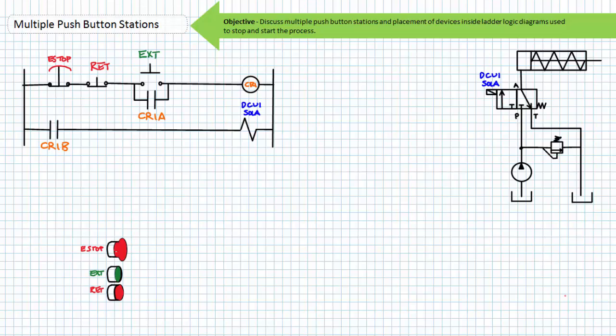That's the point of the holding circuit — it maintains the last asserted state. The cylinder would extend until the limits of travel and the pressure relief valve would open. To retract the cylinder, an operator must press the normally closed retract button. The now-open retract would de-energize the CR1 coil and the associated contacts would return to their de-energized state. The CR1A holding contact would open and remove the path in parallel to the extend push button. The CR1B contact would open, which would de-energize the A solenoid of DCV1. The spring-offset DCV1 would shift to the cross-connect position and the spring-retracted single-acting cylinder would retract. Note that all it took to initiate retraction of this cylinder is de-energizing the coil of CR1 and breaking the path for current.